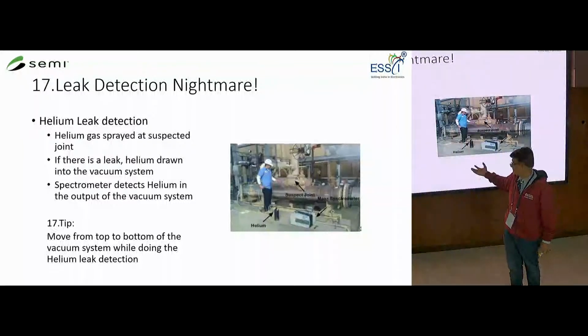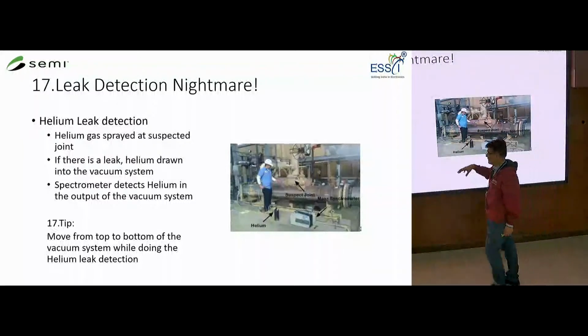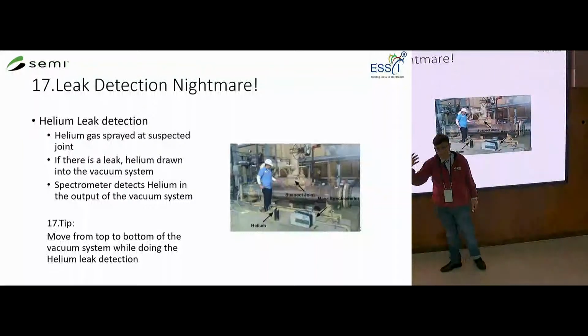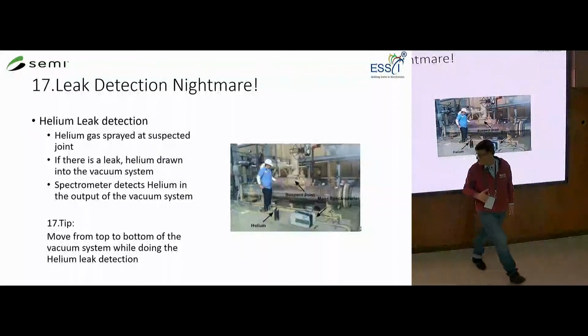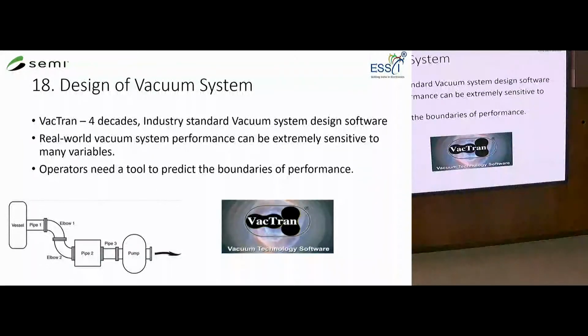If you go for a helium gas as was shared, you start with spraying it at the top of your vacuum chamber or of the system, and then you start coming down. Wherever the leak is, it will suck in the helium, and you can detect it in your output. The spectrometers will detect helium in the output. So that is the process for a helium gas leak. Move from top to bottom for isolating a helium leak.